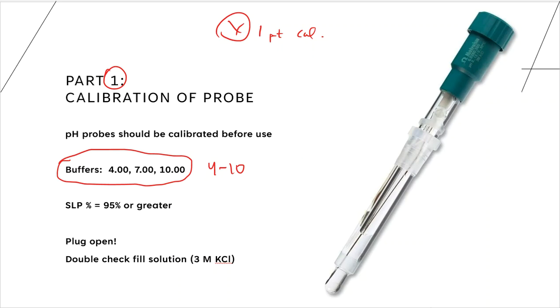1-point calibrations are common, but they are common with what I would call non-scientific probes. So if you have like a play pH probe, or a probe that you really don't care if you're just close, like this is pH of 4.7, but you know, if it tells me 6, I'm okay with it, then a 1-point calibration is going to be okay for you. So we try to stay away from these. We do not like these. Anytime you see 1-point calibration, it's phony. There really isn't such a thing as a 1-point calibration, right?